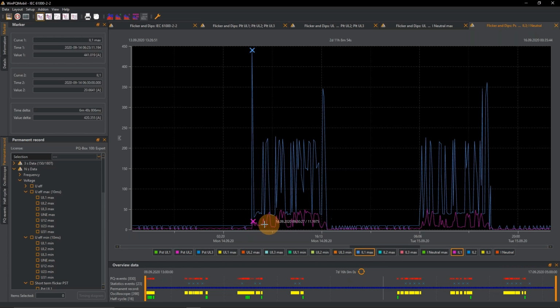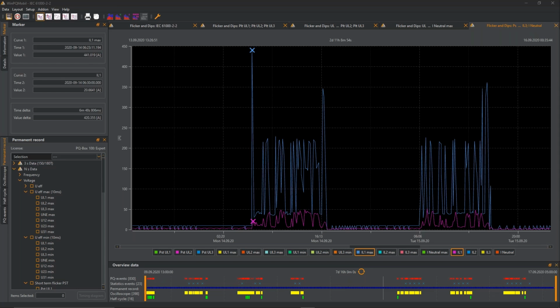So if we just have a look at the RMS values, we expect, okay, below 50 amps, that shouldn't cause any problems, but the maximum values of 400 amps, that's critical. But even though they don't cause the main fuse to trip, because our RMS values are still at around 50 amps. So here I can see the exact timestamp, of course, and each of these voltage dips I can see here. Of course, this is around 205 volts. This is not 230 volts anymore. Each voltage dip creates an event with a fault record.